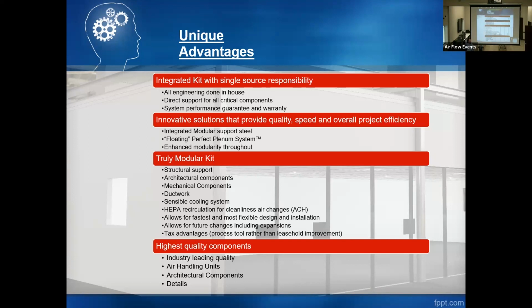And we educate them, okay, you've got to make sure you seal here, here. Typically in these units, because air leakage is a problem with ductwork, we provide the supply air and return air ductwork for the room. Typically what we'll do is install the dehumidifier as close to the room as possible. And what we've come up with in the design, and we'll see here in a few minutes, is basically a structural steel platform that goes above the room. The dehumidifier sets on top when you have the ceiling height, and then it's just short ductwork runs with completely sealed ductwork.